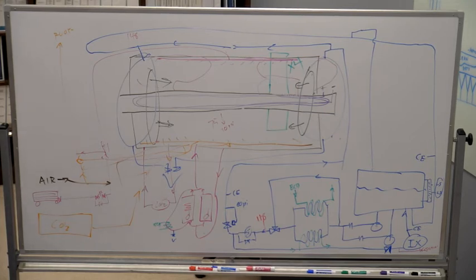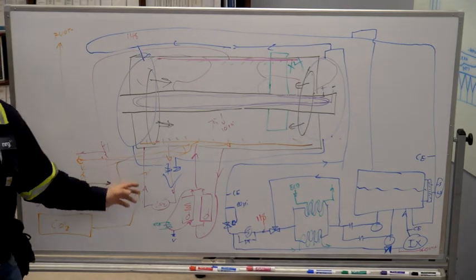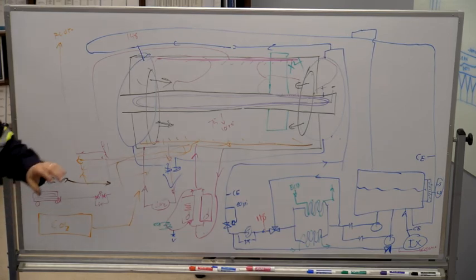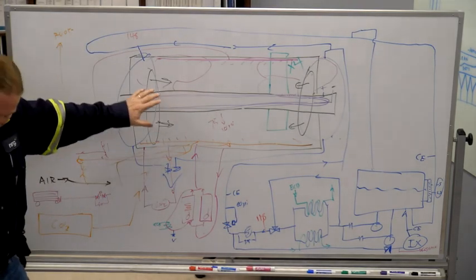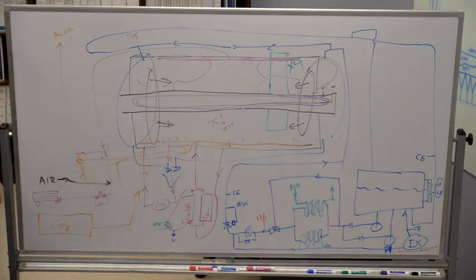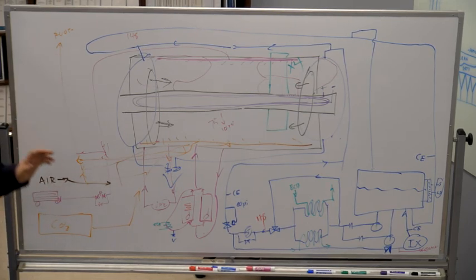And then later we're going to want to put hydrogen back in it. Before we can put hydrogen back in it, we're going to put CO2 back in it to make sure the hydrogen doesn't mix with air and at some point be between 4 and 75 percent concentration in the presence of heat and blow up and ruin our jobs. And we all have to find work somewhere else, if we're not on site.